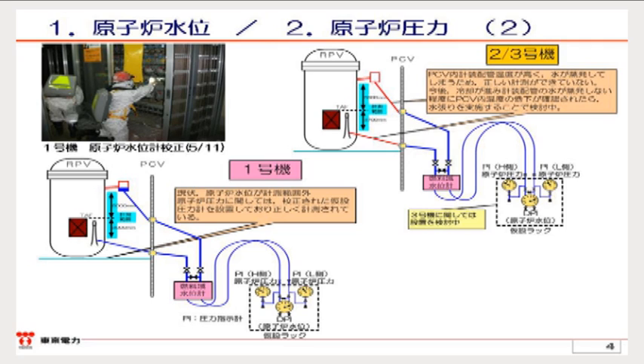The situations of Units 2 and 3 are described on the right side. As for Unit 2, we conducted a calibration once, but the water from the L side evaporated and the condensate pot has not been filled with water yet. Therefore, we think that the water level gauge is in imperfect condition. In addition, regarding Unit 3, such calibrations have not been conducted. We will develop an appropriate work plan to continuously conduct water filling in the condensate pot. Also, branching at the L side enables us to measure the pressure in the reactor. Please proceed to the following page.